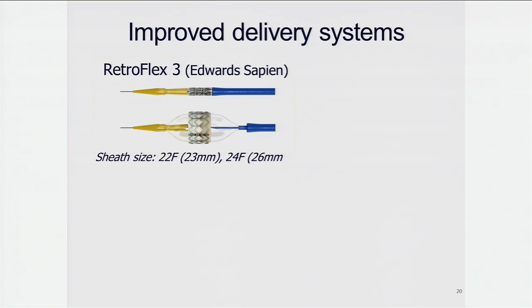We have also extraordinarily improved the delivery system. This is the RetroFlex 3. The valve is crimped over the balloon here, and this is the one used in the United States today, the only one. So, a big sheath size, 22 French, 24 French, needing more or less a cut down of the femoral artery under surgical approach. And now in Europe, we have been using for the last 2.5 years the NovaFlex delivery system, where the valve is not crimped over the balloon like this, but over the shaft of the catheter, and the valve is placed over the balloon when inside the abdominal aorta.